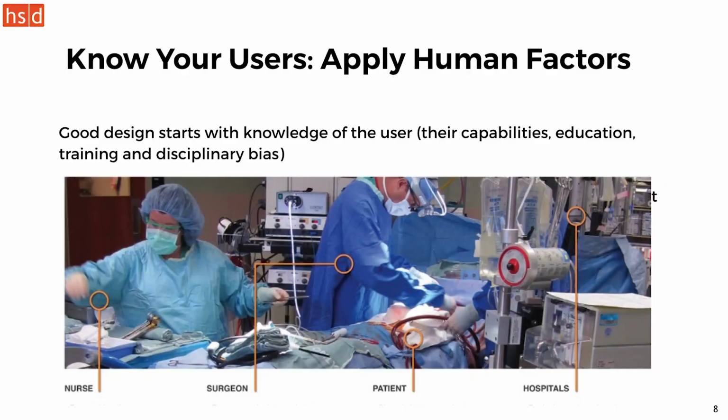Now, wearing my AAMI hat, when I look at the discussions between CDRH and CDER, for those that are in the pharma versus the device world, their definitions of harm vary. The definition of harm according to CDRH is, you know what? A little bit's okay. That's why a scalpel stays on the market, because I'm going to inherently do harm every time I do surgery. There's no possible way I can do surgery without doing some level of harm. Whereas the pharma world says, nope, no harm at all. So when we get into the combination device, it gets increasingly complex, which means that you must pay attention to use-based risk. So what does that mean when I start to do it?